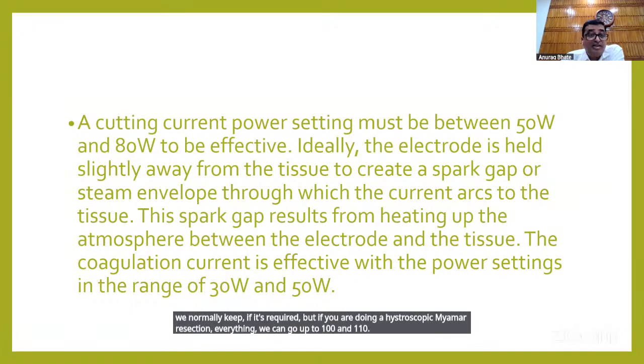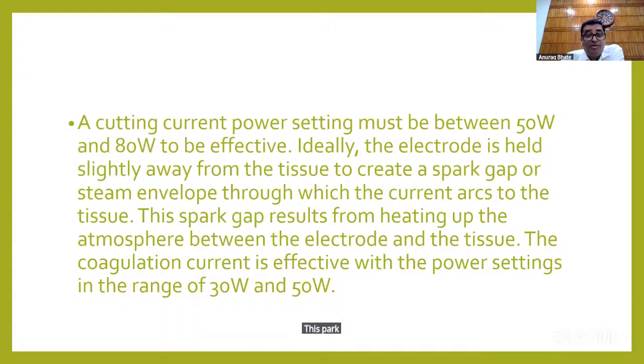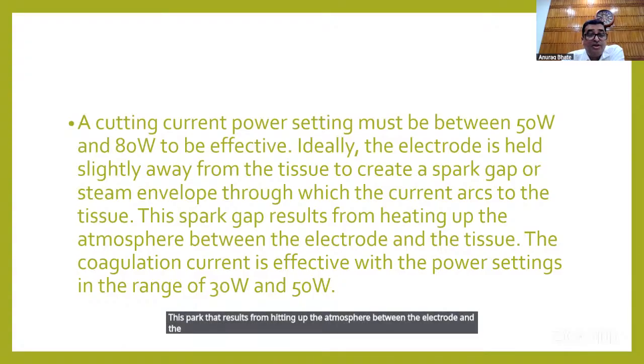Ideally, the electrode is held slightly away from the tissue to create a spark gap or steam envelope through which the current arcs to the tissue. This spark gap results from heating of the atmosphere between the electrode and the tissue. The coagulation current is effective with power settings of 30 to 50 watts. Again, same. If you ask your technicians, they will usually keep the coag setting at 40 watts.